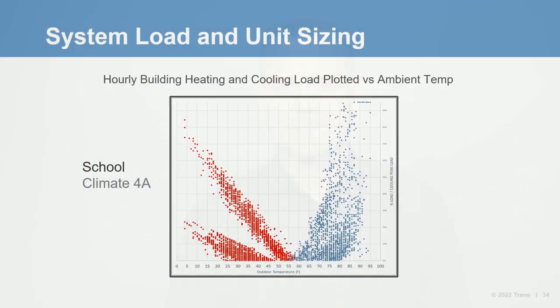In this next section, we want to start looking at how to properly size air-to-water heat pumps. We're going to start by analyzing different building load profiles in different ambient locations. First, we'll look at one specific load profile for a K-12 school in climate zone 4A. The buildings represented are the ASHRAE building models used as a basis for standard 90.1 2019. Hourly load data was extracted from Trace 3D Plus, which uses the EnergyPlus calculation engine.